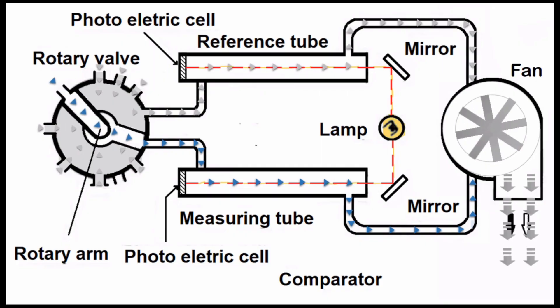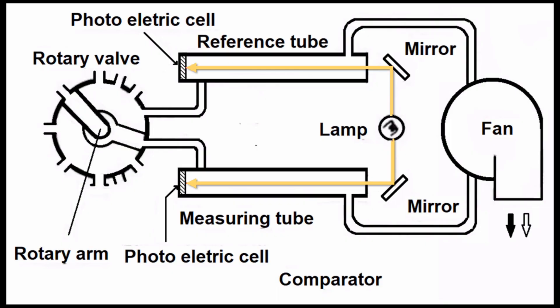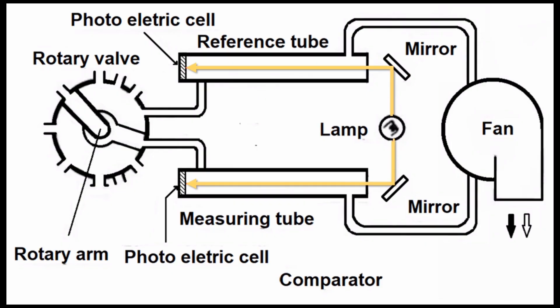If the concentration of oil mist in the measuring tube rises, the intensity of light reaching the photoelectric cell reduces. Now as both the tubes are electrically connected, reduction in the generation of electric current will induce an electric imbalance between the two cells, which will lead to ringing of the alarm.